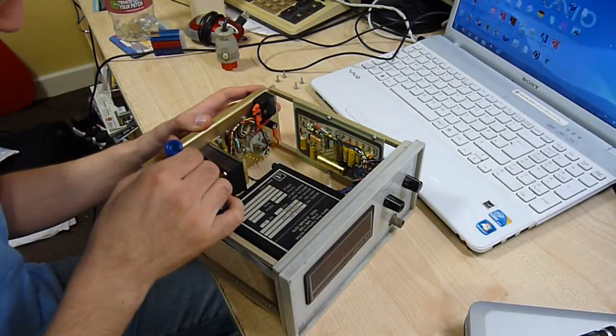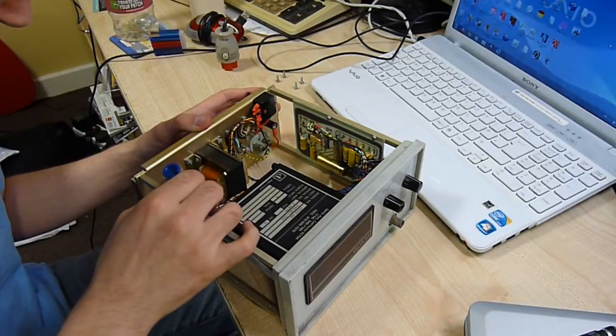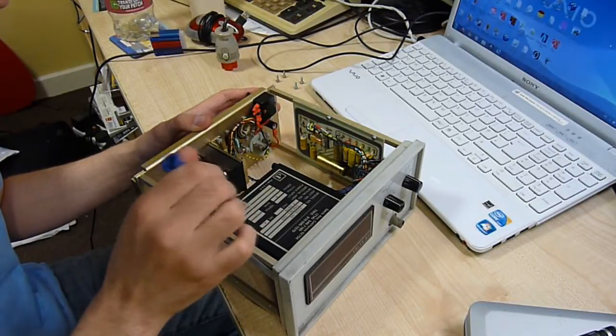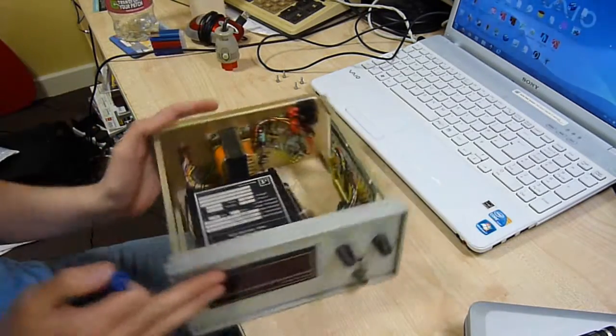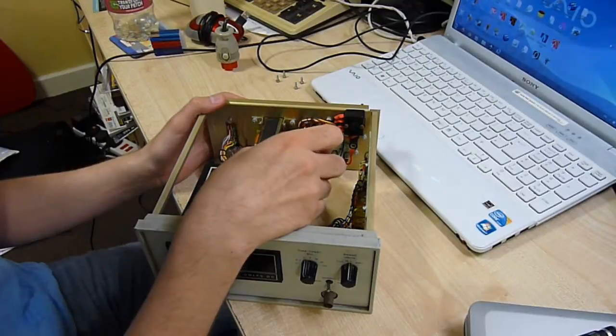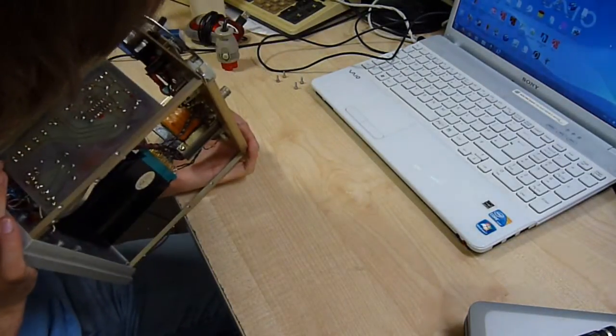All the logic is in here, which is why this is special, why it's going to be separate. Your power transformer which only has one output, which goes into this, so all the power comes from this. And there's lots of different inputs into it for different windings for whatever reason.